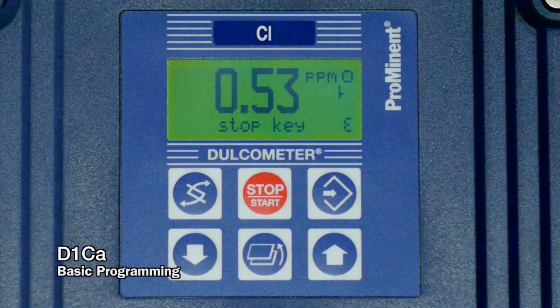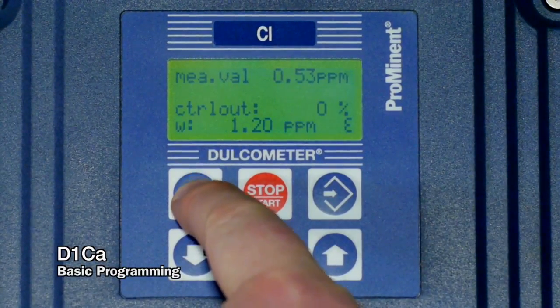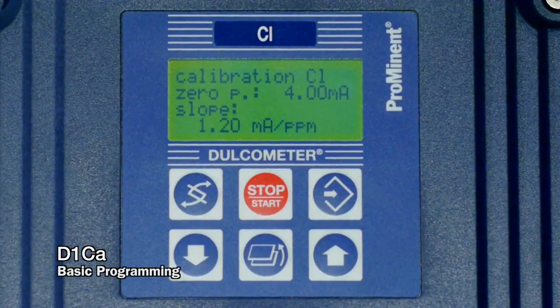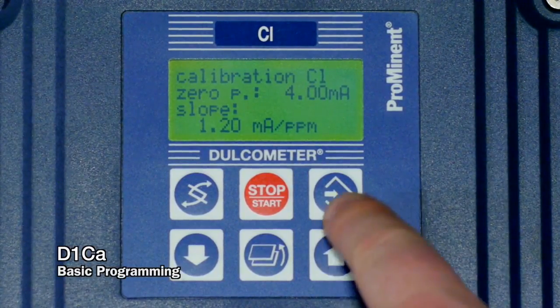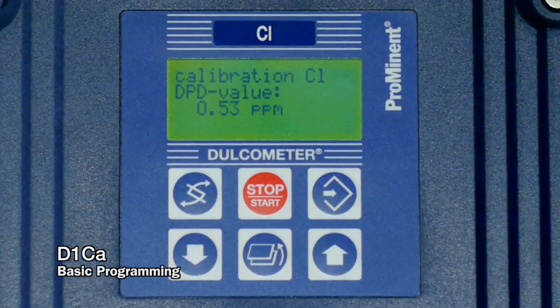To do the calibration, we're going to hit the change key, which is the top left-hand button, until we see the calibration CL screen. This is in the reduced menu, how it appears. Once we hit the enter button, you'll see the value is actually flashing. If we're in the complete menu, the verbiage DPD value is what will be flashing. We don't want to calibrate in that menu. We risk changing our 0 point at that place, and we don't want to change that 0 point.